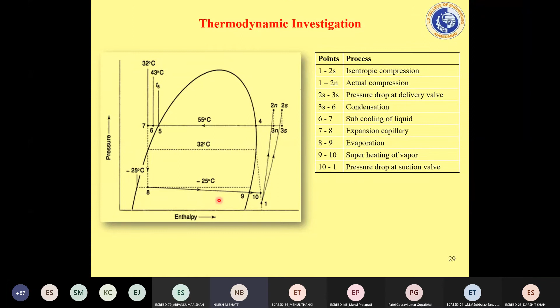You can see that the pressure drop in the condenser is negligible while the pressure drop in the evaporator is significant. I will not elaborate, but I will just recall that in the evaporator, the frictional as well as momentum pressure drop are both positive, while in the case of the condenser, the frictional pressure drop is positive while the momentum pressure drop is negative. That means there is a momentum gain because of the condensation of the liquid. So that is the reason the condenser pressure drop is almost negligible while there is a significant pressure drop in an evaporator. And that is the reason the condenser could be oversized, but normally the evaporators are not oversized in domestic refrigerators or even in any refrigeration system.